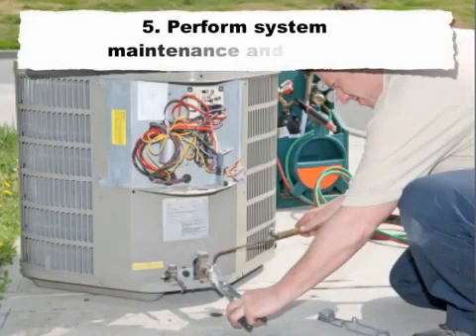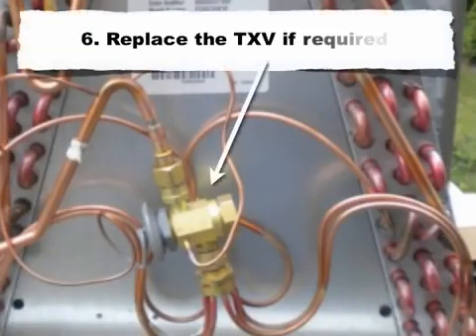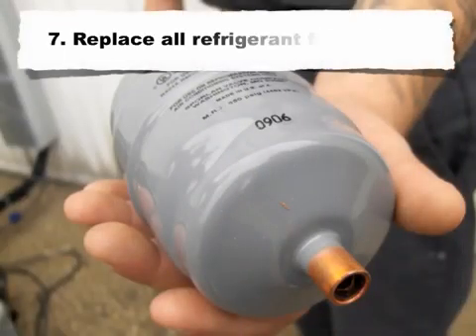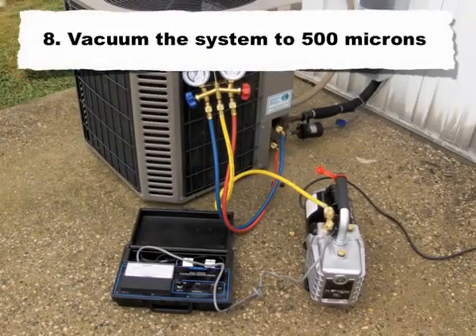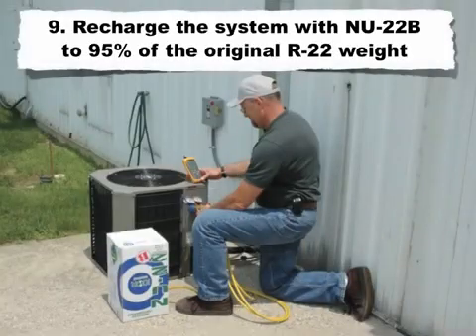Step 5: perform system maintenance and repairs. Step 6: replace the TXV if required. Step 7: replace all refrigerant filter dryers. Step 8: vacuum the system to 500 microns. Step 9: recharge the system with NU-22B to 95% of the original R22 weight. Do not charge by sight glass, as it could lead to an overcharge.